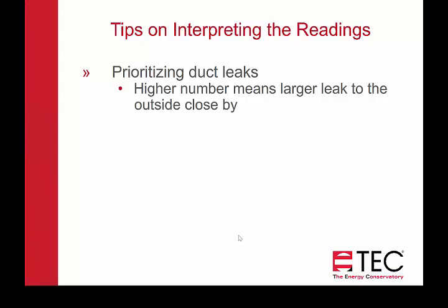Next we'll go over some tips on interpreting those readings — part of this is prioritizing which ducts you're going to go after first and which ones you're going to seal. Higher numbers means the larger leak to the outside is close by. If you get a high reading on that duct run or return system, that means you're closest to the biggest leaks in the system.